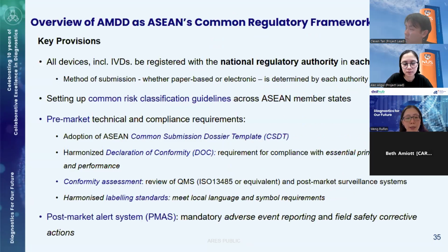So under the AMDD, while all devices still need to be registered with the respective national regulatory authority in each ASEAN country, the AMDD really sets out common guidelines for product risk classification across the region, while it also provides a set of common technical and compliance requirements that are required for both pre-market product review as well as post-market surveillance and reporting.